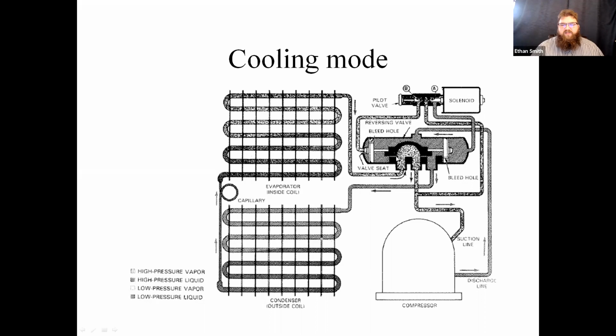And the way these valves work is in cooling mode, that little clamshell is going to bridge between the center pipe, which is our suction, and the pipe that comes from our indoor coil. Okay, so refrigerant is moving through our indoor coil, comes in as a vapor, hits that little clamshell, and then shoots it back into the suction line of the compressor.